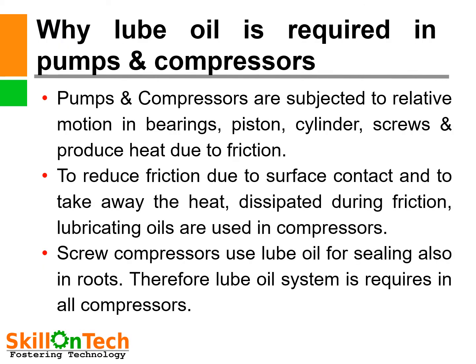Lube oil is required in pumps and compressors because they are subjected to relative motion in bearings, pistons, cylinders, and screws, which produce heat due to friction. To reduce friction and take away the heat dissipated, lubricating oils are used. Screw compressors also use lube oil for sealing, so a lube oil system is required in all compressors.